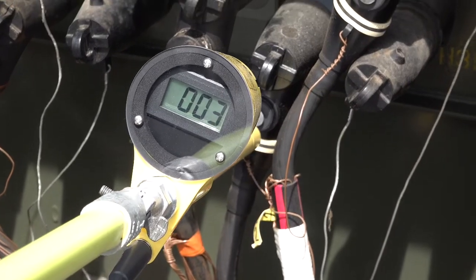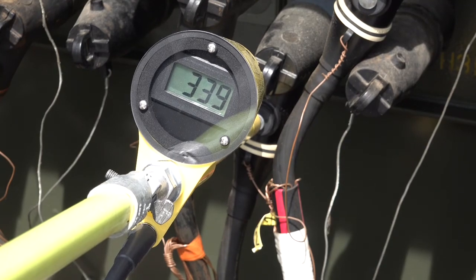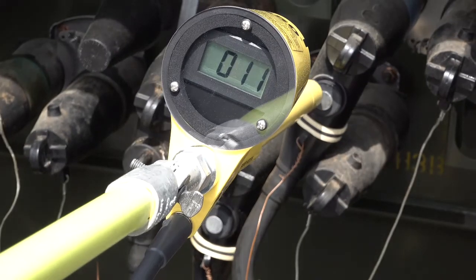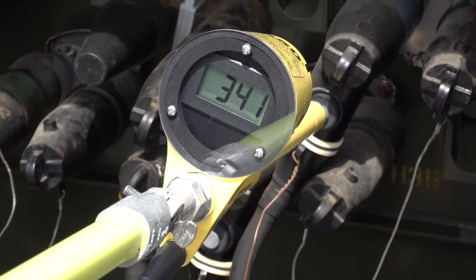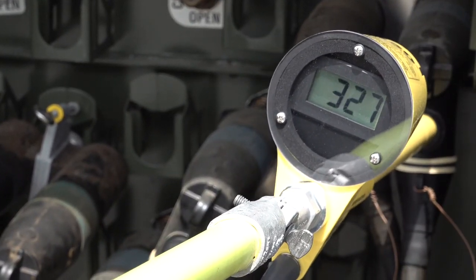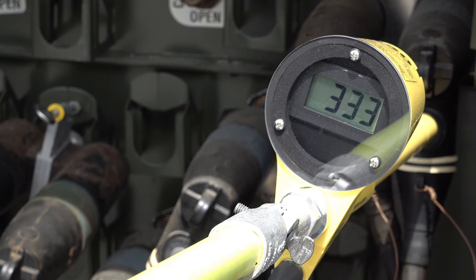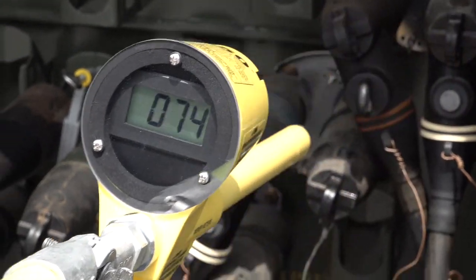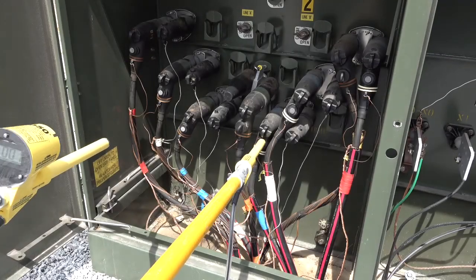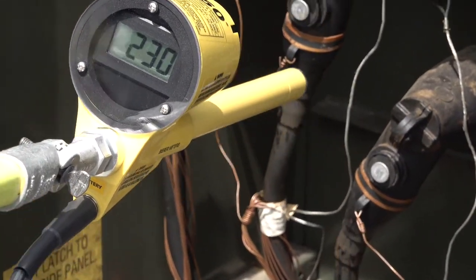When phasing capacitive test points using the PD50, since it is an extremely accurate, within 1%, true RMS high voltage meter, check each capacitive test point to ground and first determine if the capacitive test point is energized and/or in good condition. Also, we want to determine if any dissimilar voltages are present due to different manufactured elbows. Note how the readings of these capacitive test points are very similar potentials, less than 10 volts of separation. That is because they are from the same manufacturer and also of the same age. After we have checked all the capacitive test points' potential to ground, we can begin phasing.